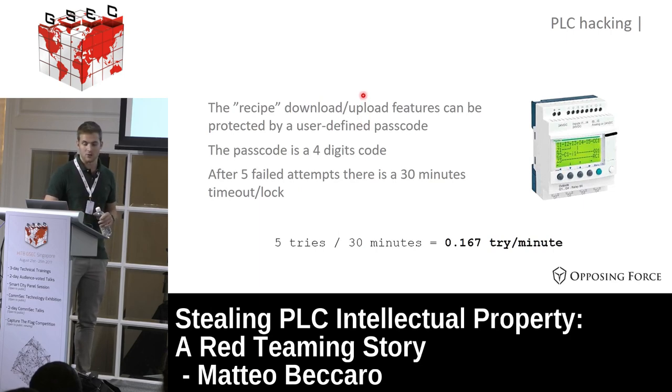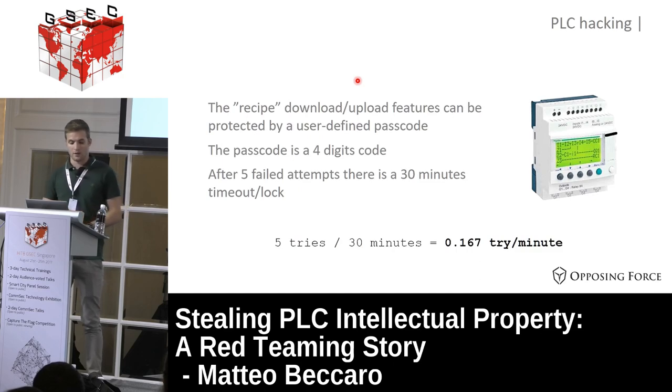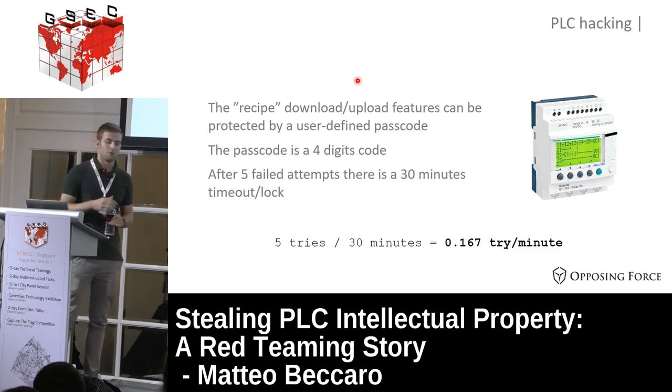We found that there is a download and upload feature in the PLC that can be protected by a user-defined passcode. The passcode must be provided to the software before downloading a recipe from the PLC, and also during upload from computer to PLC. If you forget the password you have to reset the PLC memory. The passcode is only a four-digit code. Initially we thought we could brute force it, but after five failed attempts there's a 30-minute timeout lock, meaning we could try only 0.16 passcodes per minute - far too slow.